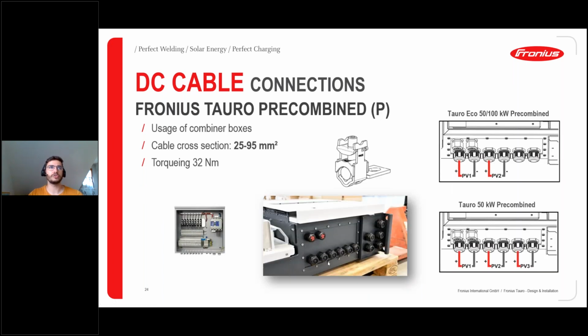Let's have the same closer look on the Tauro precombined, short P. And the precombined is again the topology for a direct version where we have a central version where all the inverters are collected at one place, and we have bigger DC cables coming from the DC combiner boxes from our field. And there we have those V-clamps. Here is a schematic how this looks like. And these V-clamps can handle up to 95 square millimeters on the DC side. And as we can see here down below, this is how it looks like with the cable glands.